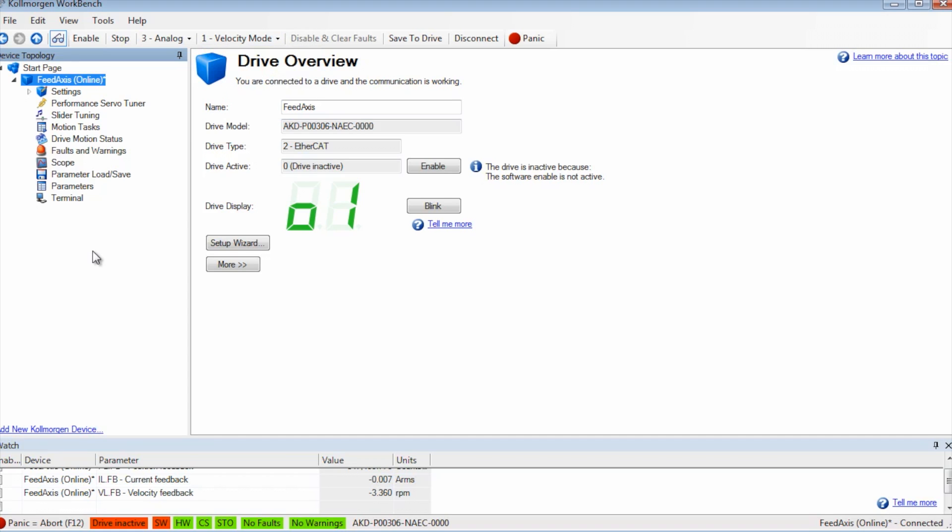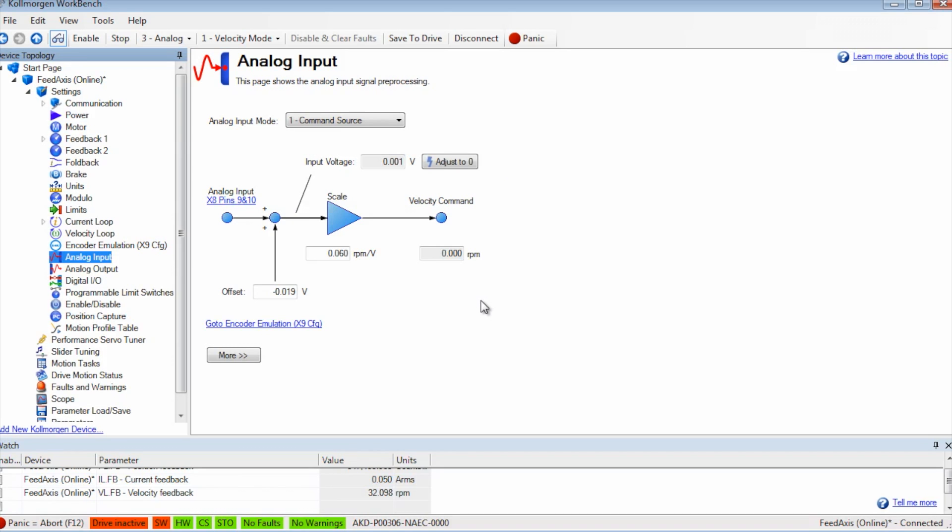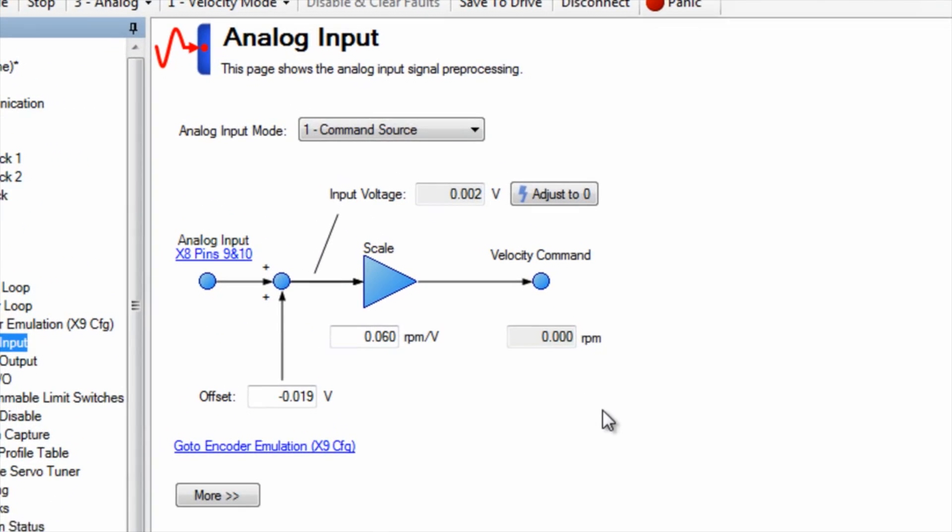Once set we can go into the analog input screen. The scale is set to provide the greatest range possible with the input command. With a command of plus minus 10 volts we set the scaling by using the maximum velocity of the motor divided by 10.